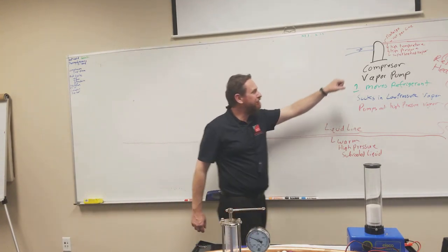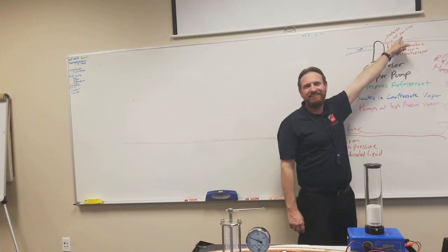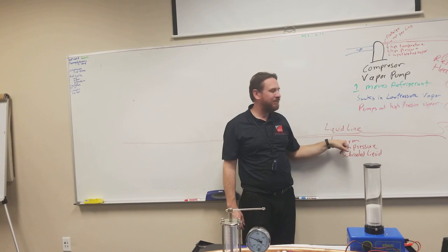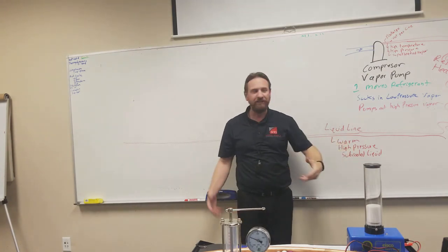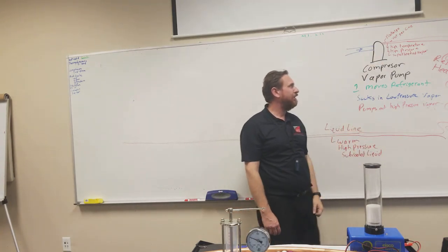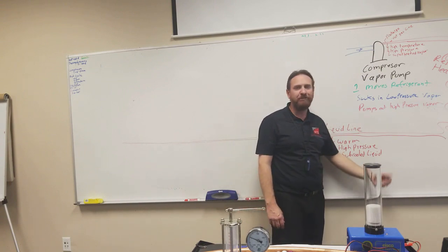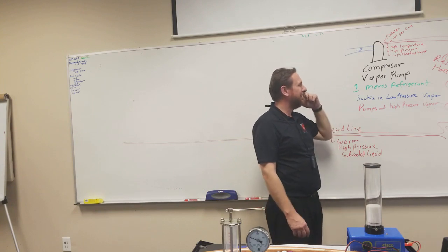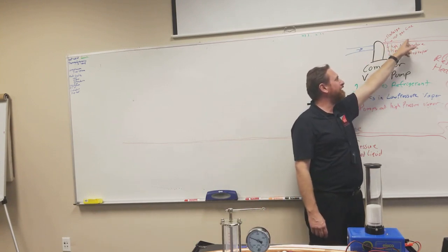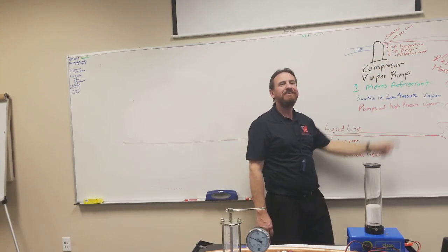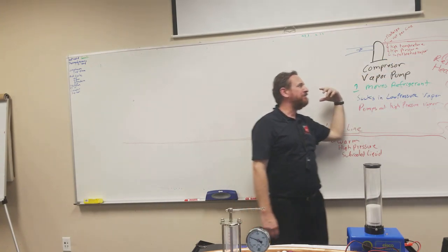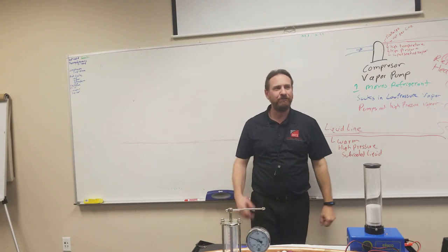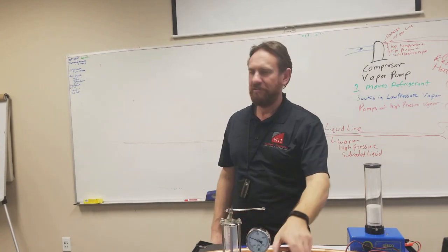So if you feel it here, what's the name of this line? Hot gas. Hot gas line. And now if I was to grab the line here, it's going to be warm to you, to your feelings. This will be hot and this will be warm. But according to the refrigerant, it's a subcooled liquid. We'll get there later. So which one will be hotter, this line or this line? The hot gas one. The hot gas line. What happened is the refrigerant got rid of some of its heat, but it's still going to be warm right here to you and your feelings. Okay? So far, so good?